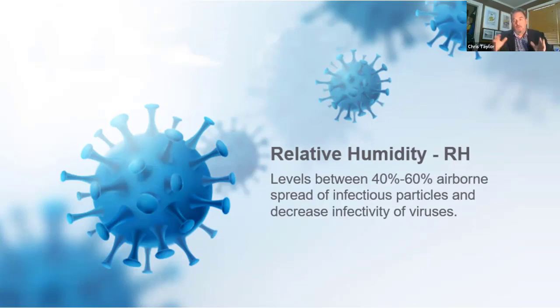So while 40 to 60 is our target, what I will say is with the balance of looking for condensation, if you're not seeing condensation and you can get above that 20% range, that might be where you're trying to manage and balance risk and reward in this kind of scenario. Just like filtration, better filtration is good, but reduced air is bad. So how do I find that balance? If you're seeing condensation, the risk for mold and damage to your building systems is probably greater than dropping that humidity down a little bit into that lower range.